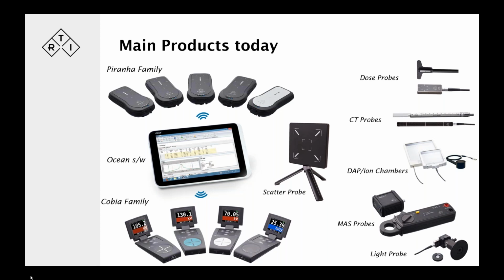So this is the package. These are the probes that we have, and the latest addition to it is, of course, the scatter probe, which we introduced last year, which, as the name tells you, measures the scatter. So it's used for scatter and leakage measurements in the X-ray field. And what we have here is the first, or one of the few, with 100 square centimeter effective area to measure, which conforms to the regulation in this field for leakage and for scatter. And there's also the 10 square centimeter, which is required in some of the regulations for secondary radiation, barrier radiation.